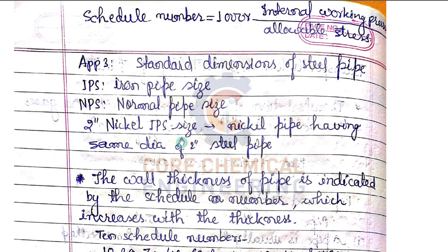Schedule number equals 1000 times internal working pressure divided by allowable stress. When a fluid flows through a pipe, it exerts internal pressure on the piping system. For example, in a steam line, you can read the pressure from a pressure gauge or pressure transmitter. That pressure is the internal working pressure, which divided by the allowable stress and multiplied by 1000 gives the schedule number.